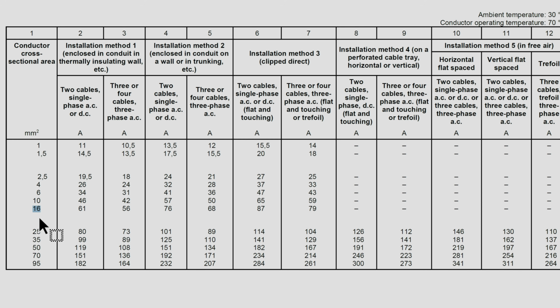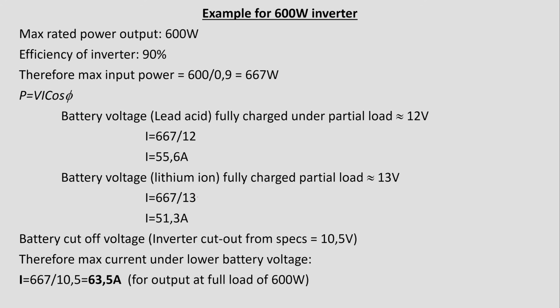Because the current is so high, we don't want to lose voltage just because of a thinner cable, because it will mean that the battery will have to work harder. But recall from the earlier calculation, if the voltage at the battery is 13 volts, or the voltage coming into the inverter is 13 volts, I only need 51.3 amps. But if the voltage coming into the inverter is a bit lower, look what happens to the current. And that means the battery has to work harder in order to provide a higher current.